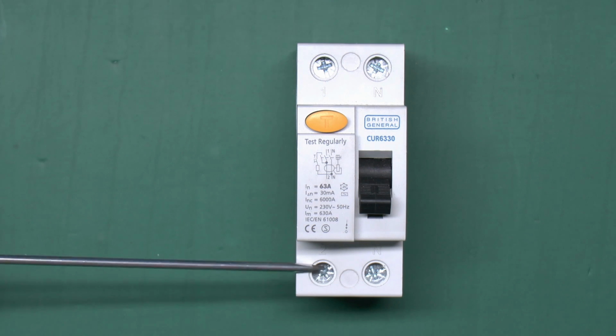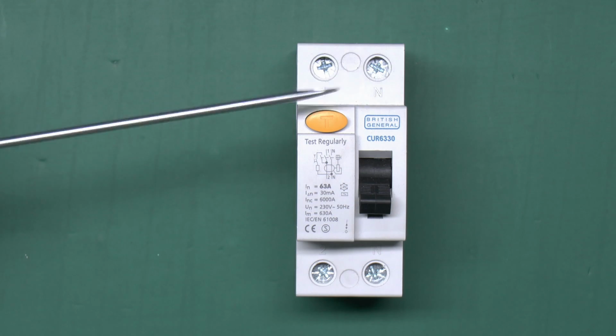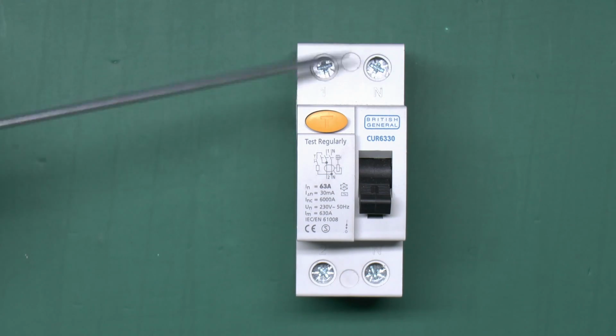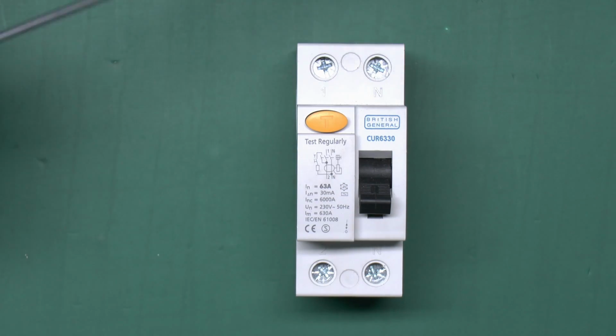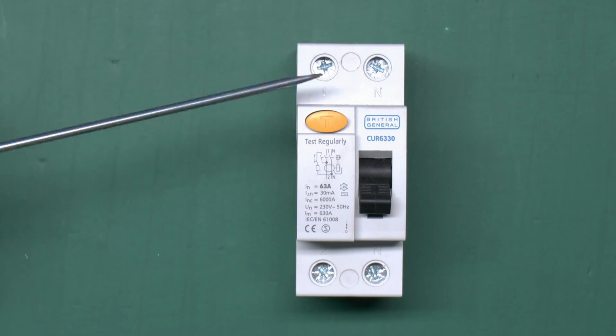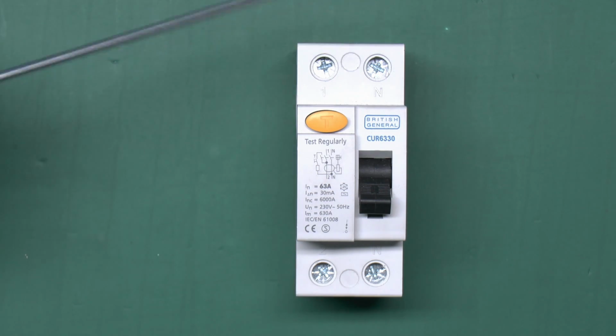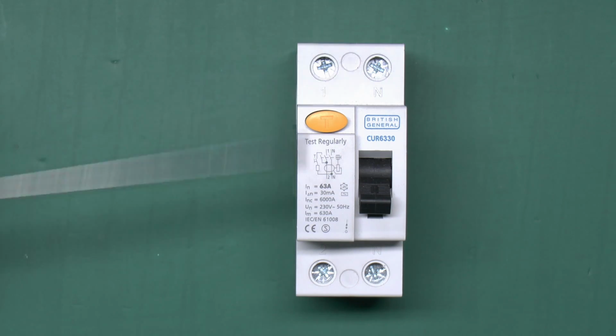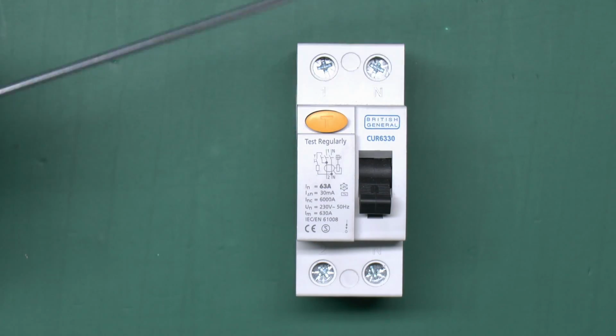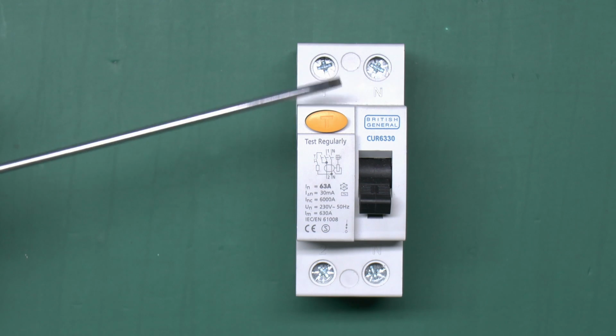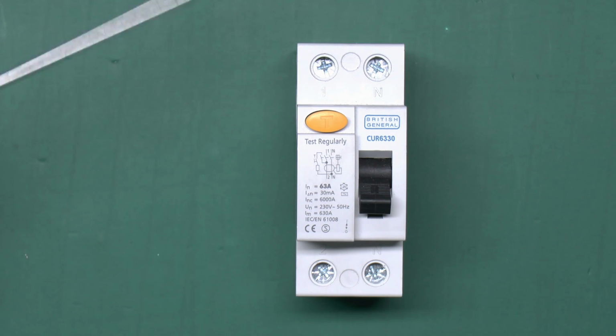And these will always have a connection to both line and neutral because they work by monitoring the current flowing through the device, so obviously through the line and then returning via the neutral. And in normal circumstances, of course, those two currents should be exactly the same. If a fault occurs on the load side of the device and the current can then flow to earth via some other path, the current flowing through here is not going to equal the current coming back, and in those circumstances the device will trip and disconnect the supply.